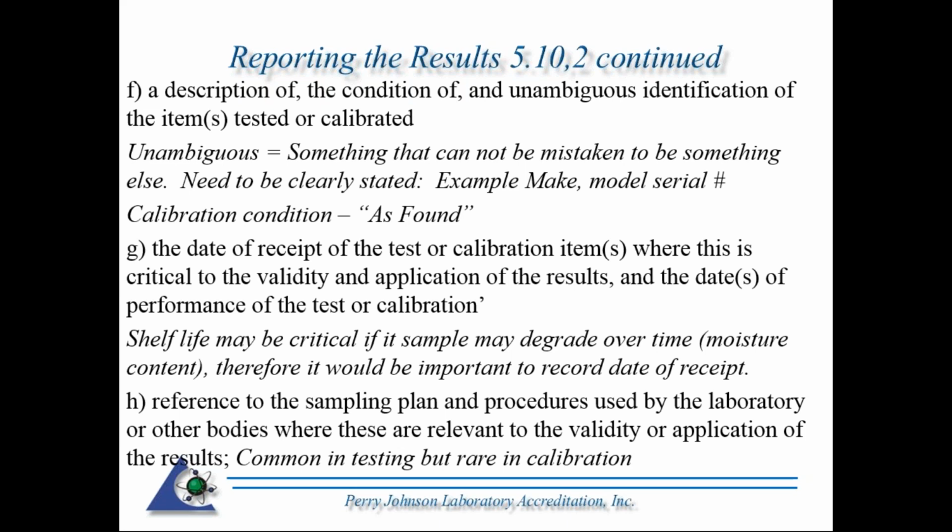G, the date of receipt of the test or calibration items, where this is critical to the validity and application of the results, and the dates of the performance of the test or calibrations. So again, this is where it's critical to the validity. That will come into play where perhaps shelf life may be critical if a sample may degrade over a period. Something that comes to mind that I was once involved in was moisture content.